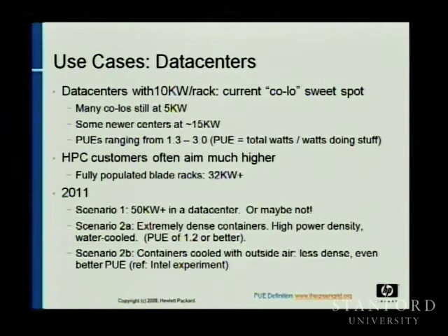And if you have a PUE of 2 and above, you haven't calculated it, right? You just say, oh, we don't know what ours is. And the high-performance computing customers are kind of different. They will routinely put in clusters with 30-plus kilowatts a rack. They're willing to break the rules and build custom data centers because there are advantages to increased density for them.